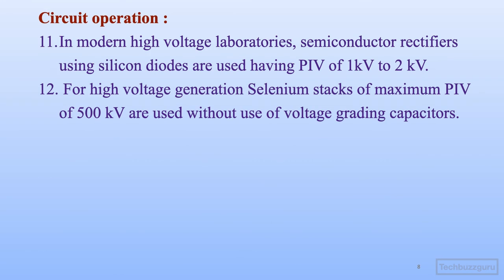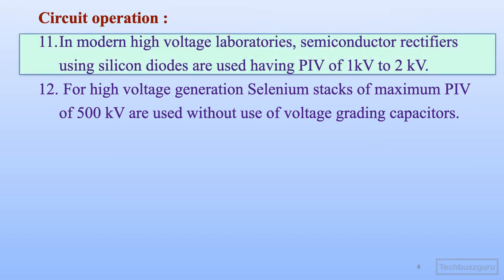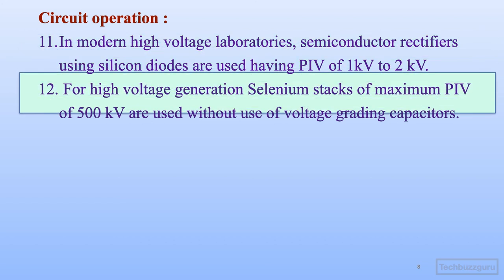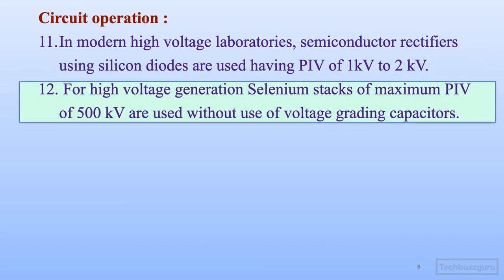In modern high voltage laboratories, semiconductor rectifiers using silicon diodes are used, having a peak inverse voltage of 1 kV to 2 kV per diode. For higher voltages, several silicon diodes may be connected in series along with voltage grading circuits. For high voltage generation, selenium stacks with a maximum peak inverse voltage of 500 kV are useful and do not require voltage grading capacitors.